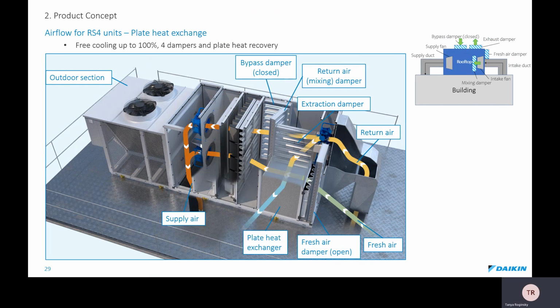The RS4 unit version, this rooftop range, is the most energy-efficient solution. We have two modes available. Heat recovery mode, where the plate heat exchanger is active, or bypass mode, where the fresh air is directly supplied to the building. To allow for both modes to work, the unit has 4 dampers with only 3 working at any given time.